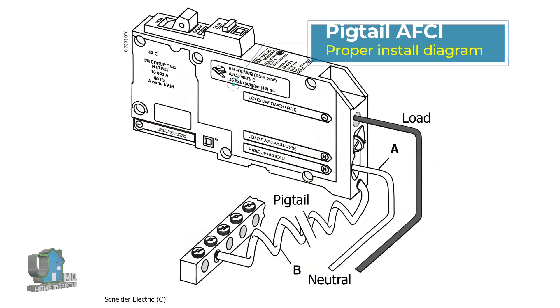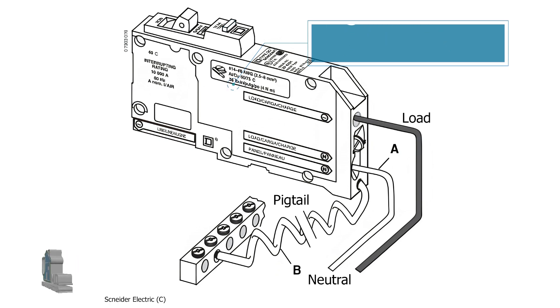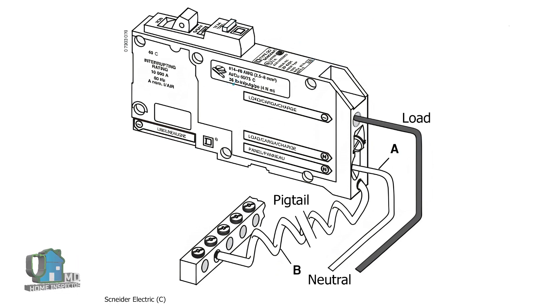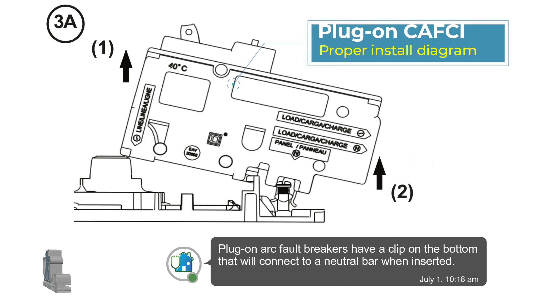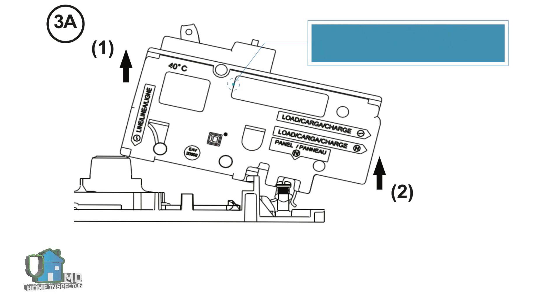There could also be improper installation of the arc fault breaker. Proper AFCI wiring is fairly simple: for pigtail style breakers, the white pigtail is connected to the neutral bar, with two terminals — one for power and one for the neutral wire. Updated arc fault breakers are even easier because the pigtail has been eliminated in favor of a plug-in neutral style connection made automatically when you plug the breaker into the panel.